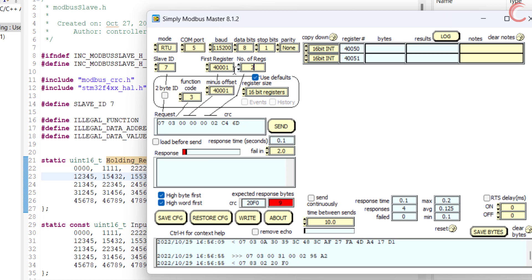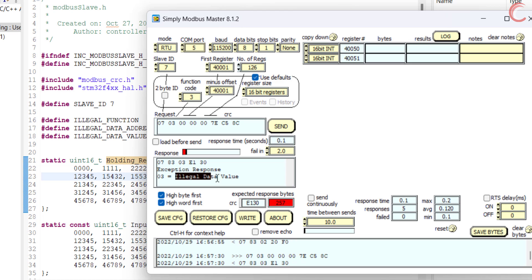So we saw the exception for the data address. Now let's see the exception for the data value. Let's say the master wants to read 126 registers starting from 40001. We know as per the standard the master can request a maximum of 125 registers. Since the master has requested 126, the slave will send an exception about the illegal data value.